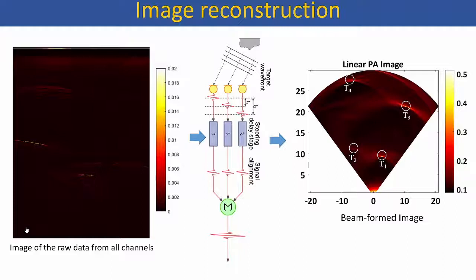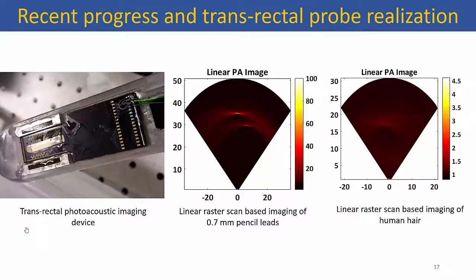We can image as deep as around 2.5 centimeters in this case. Going ahead, we have now put together linear arrays in a light guide, where light comes out from two rectangular openings connected via a bundle of optical fibers to a laser source — making this a complete photoacoustic probe in development. It will be a handheld probe designed for transrectal imaging applications, mainly targeted toward prostate cancer imaging. The linear array is wire bonded to multiple points and we are still working on connecting all elements for multi-channel data acquisition to get continuous images.